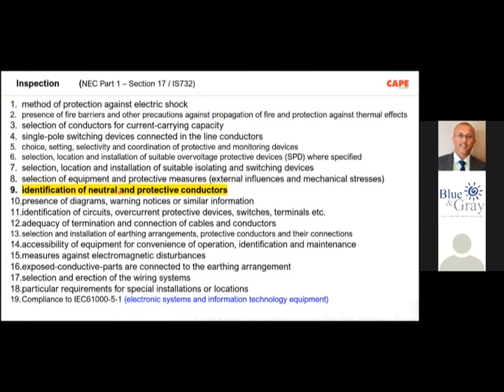Number 9, identification of neutral and protective conductor. As I said, the regulation is that a minimum of 1 mega ohm insulation resistance between live conductors and the earth is the minimum requirement. This also means a minimum of 1 mega ohm insulation resistance is required between neutral and protective conductor inside your electrical installation. If we violate it, we are actually ending up with trouble.